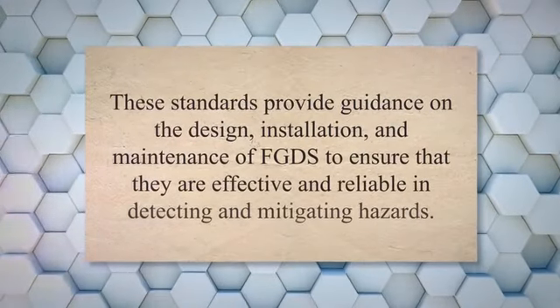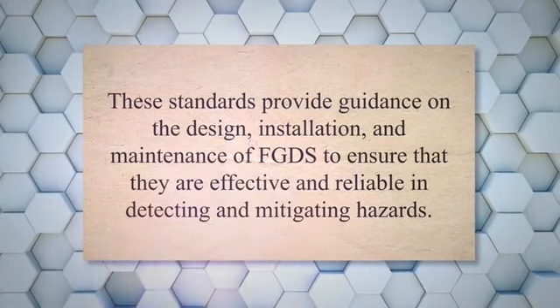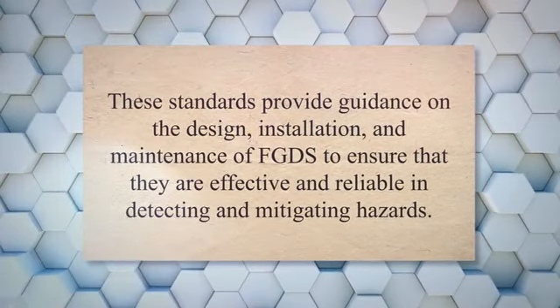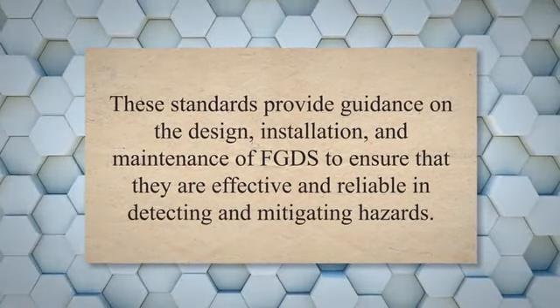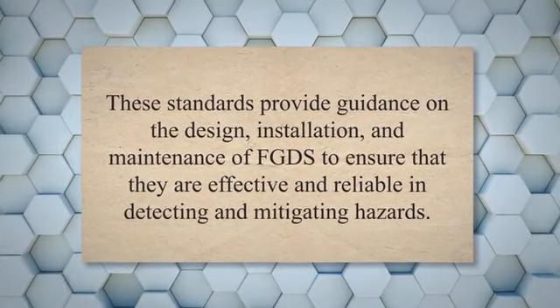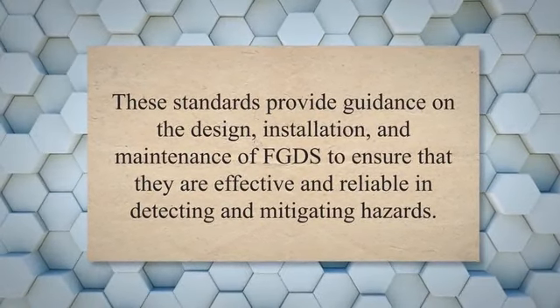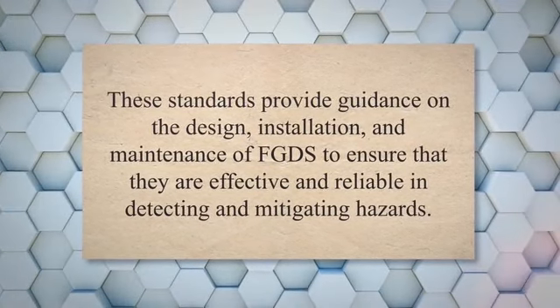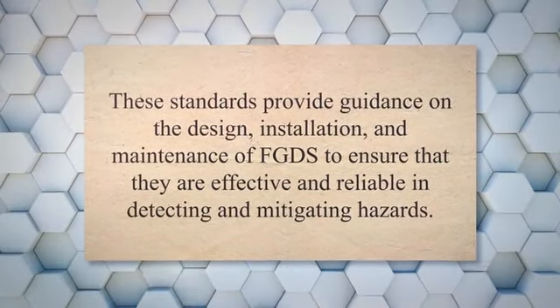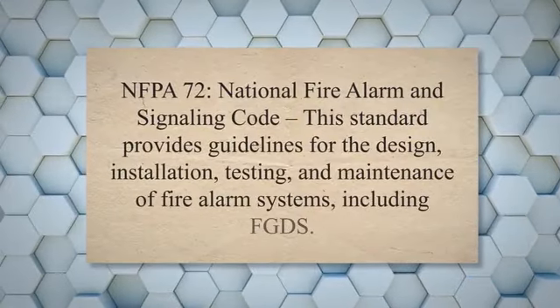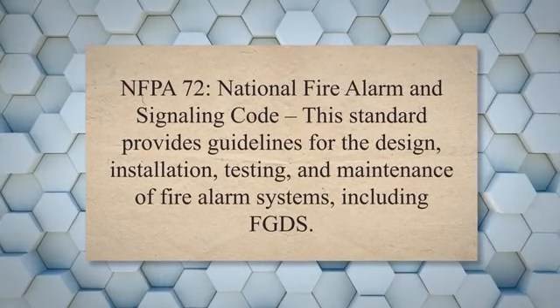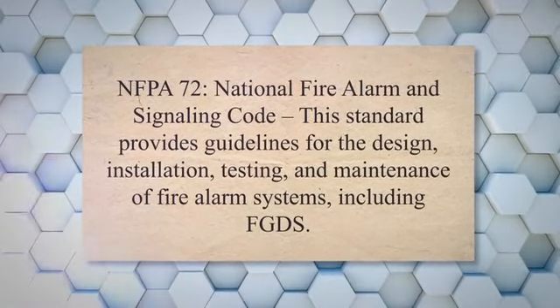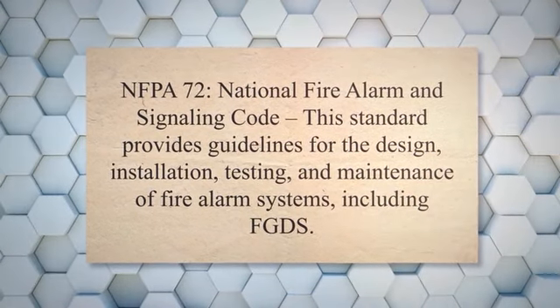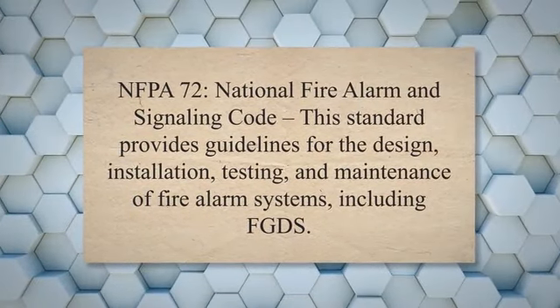Several design standards exist for fire and gas detection systems, FGDS, in the oil and gas industry. These standards provide guidance on the design, installation, and maintenance of FGDS to ensure that they are effective and reliable in detecting and mitigating hazards. Here are some of the most commonly used standards. NFPA 72, National Fire Alarm and Signaling Code. This standard provides guidelines for the design, installation, testing, and maintenance of fire alarm systems, including FGDS.